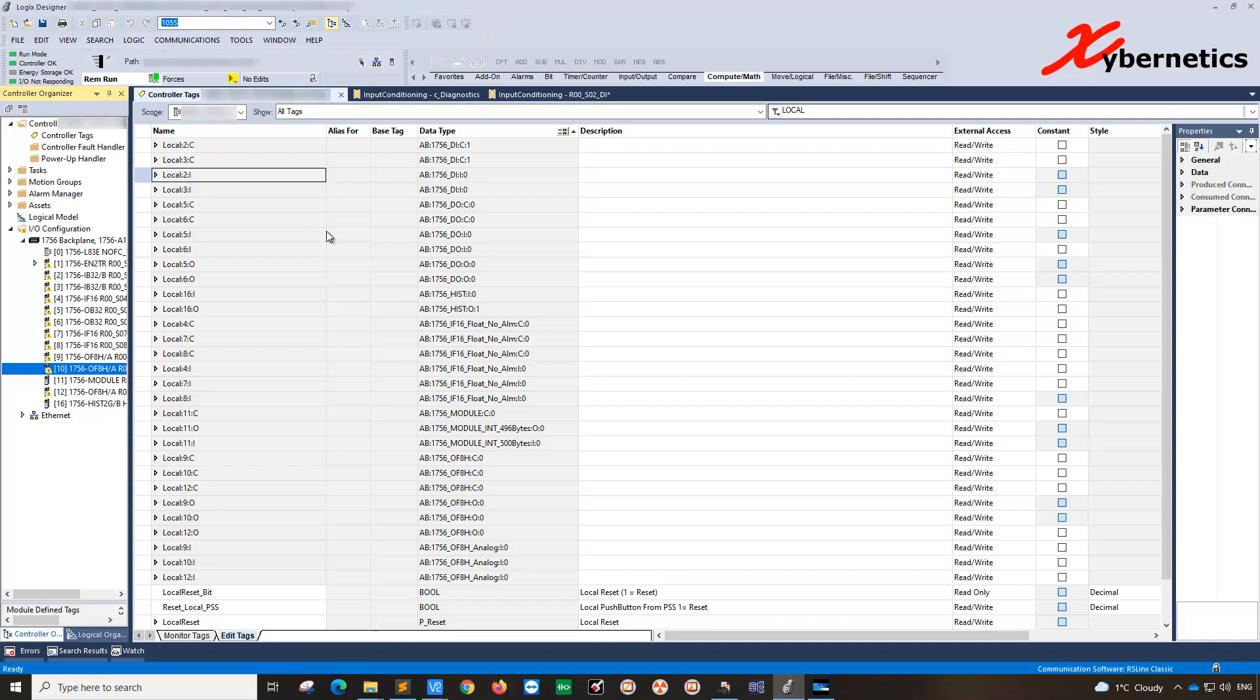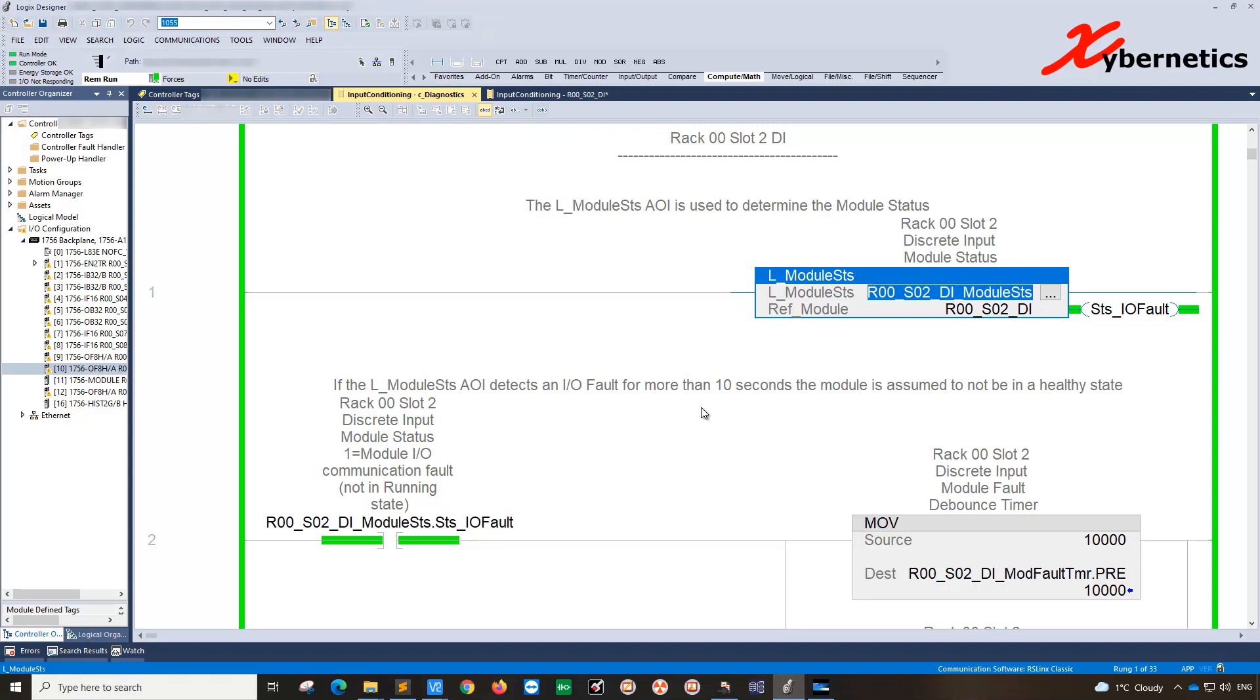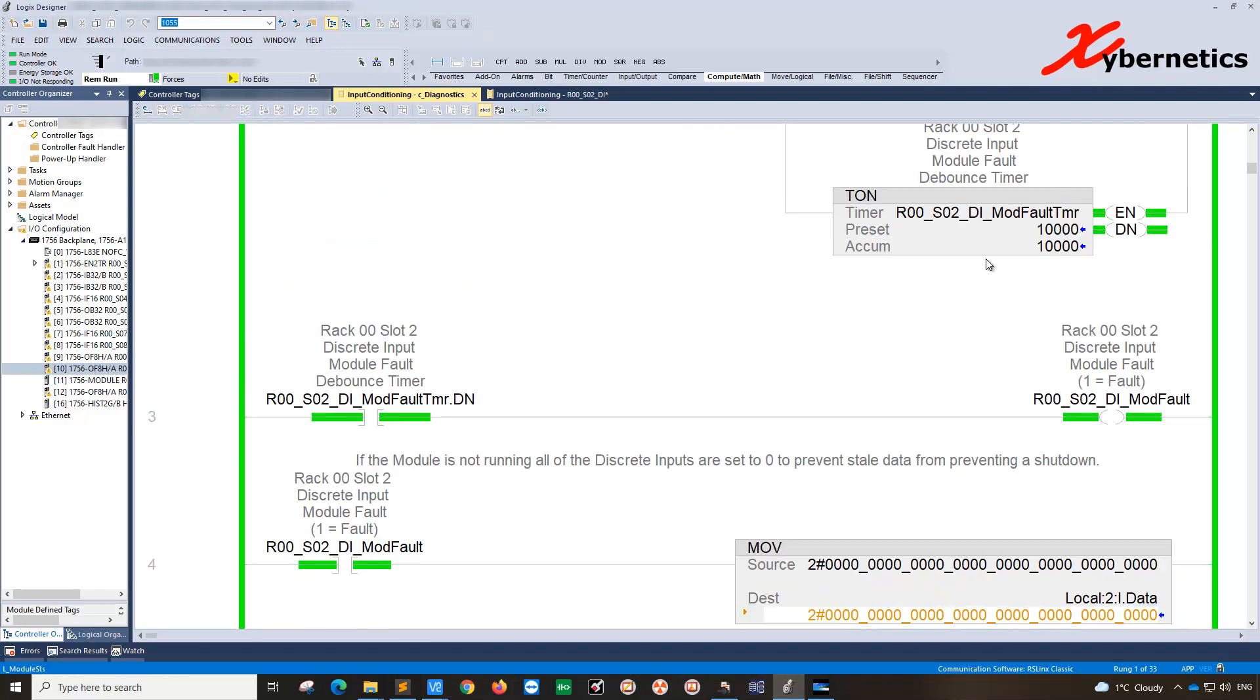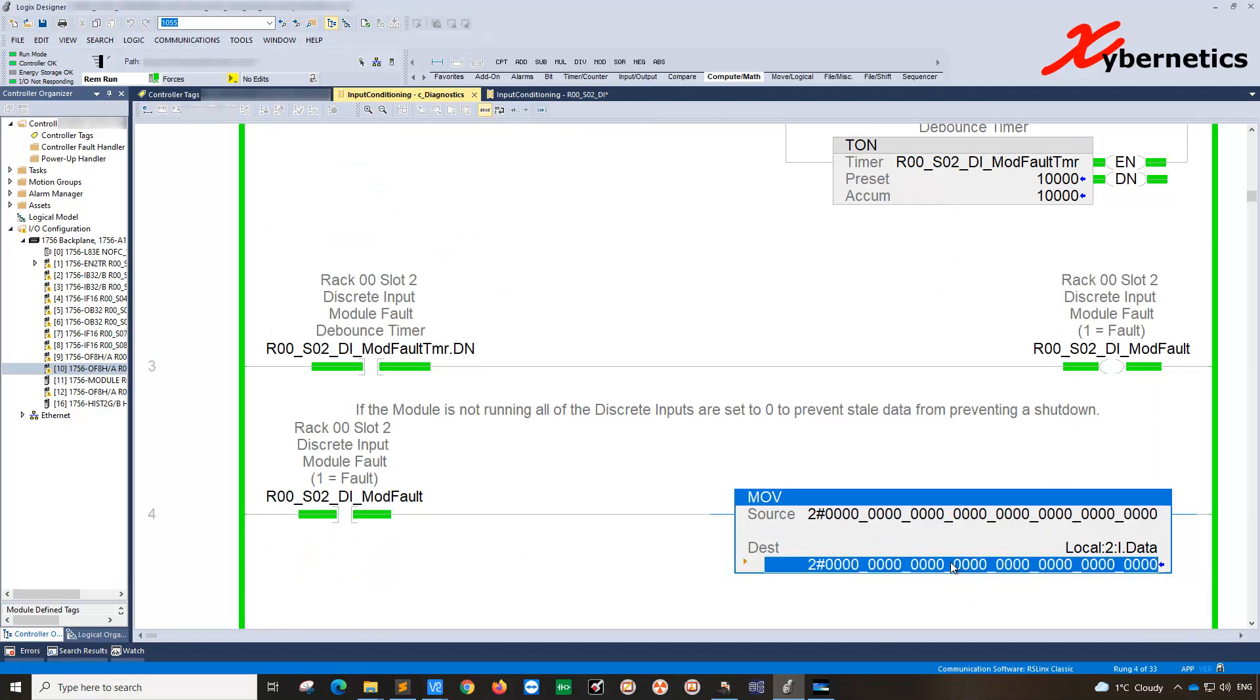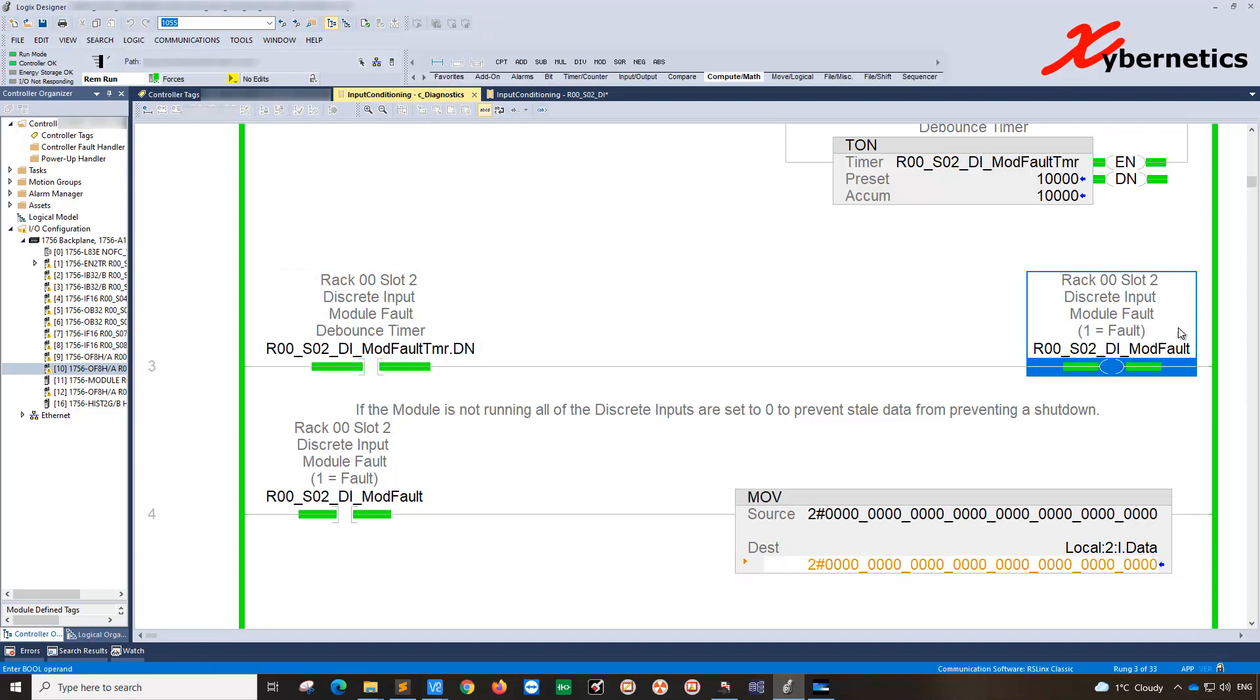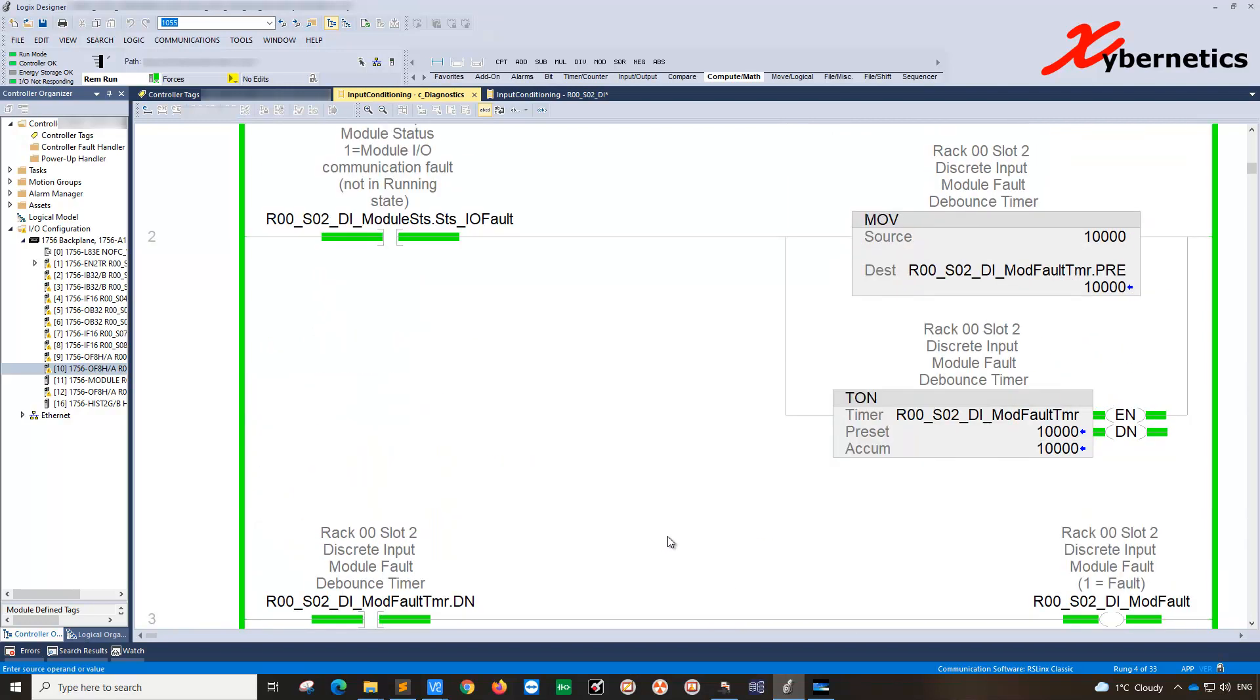For example, I have a program that's actually straight from Rockwell that checks the status of the modules. If the module is faulty, after 10 seconds it sets all the values to zero. That's just the way they did it. The default time expires after 10 seconds and it issues an alarm on the HMI.